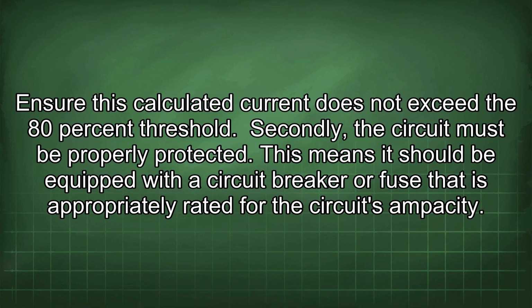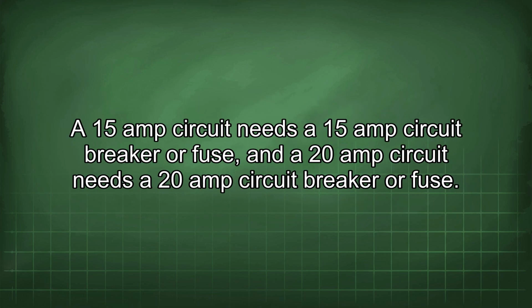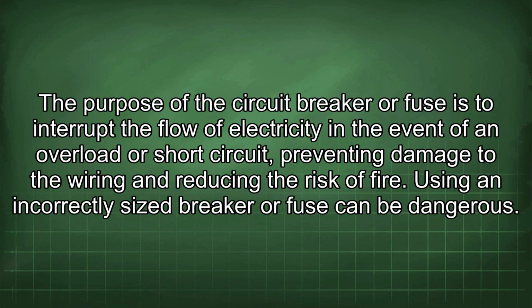Secondly, the circuit must be properly protected. This means it should be equipped with a circuit breaker or fuse that is appropriately rated for the circuit's ampacity. A 15 amp circuit needs a 15 amp circuit breaker or fuse, and a 20 amp circuit needs a 20 amp circuit breaker or fuse. The purpose of the circuit breaker or fuse is to interrupt the flow of electricity in the event of an overload or short circuit, preventing damage to the wiring and reducing the risk of fire.